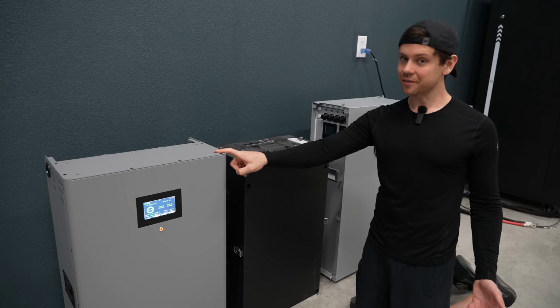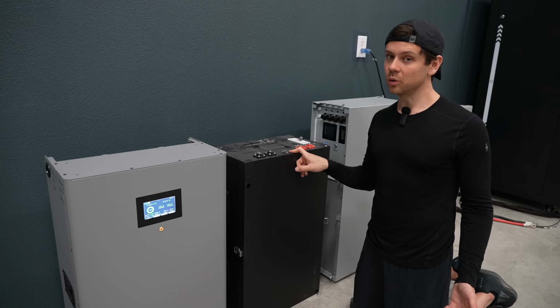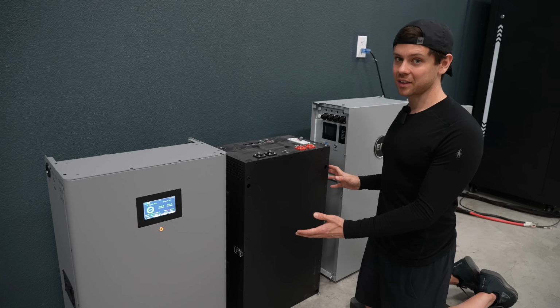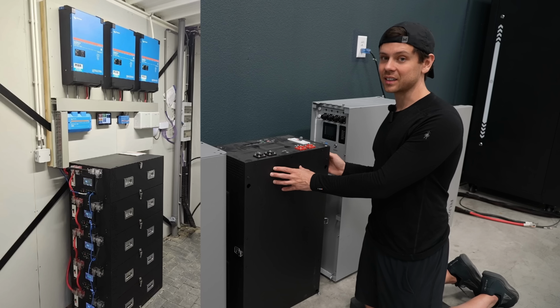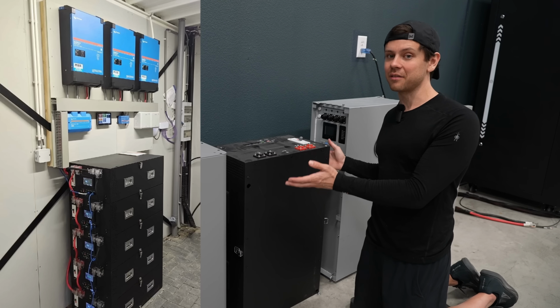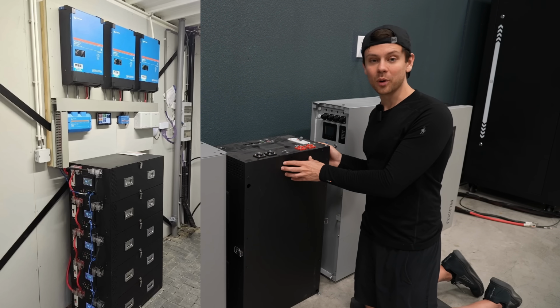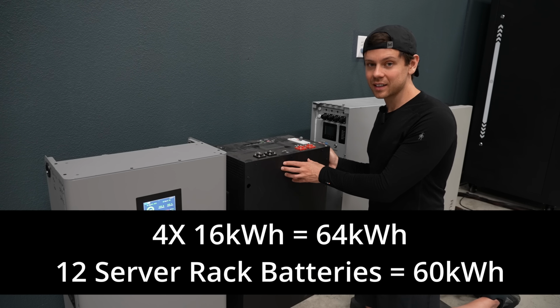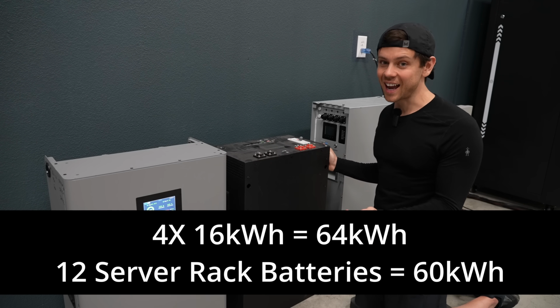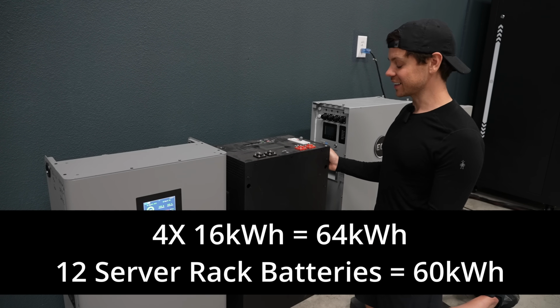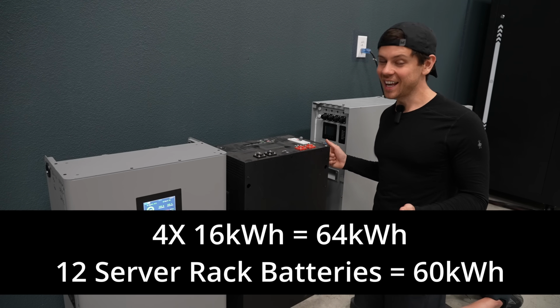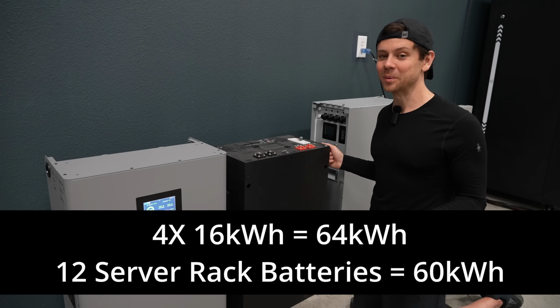Besides the fuse, I still like the horizontal one better because you can stack them. This has the best volumetric density out of, I think, any battery I've ever tested. If you stack 4 of these, you'll get the same capacity as 2 server rack stacks, which is crazy. But is it code compliant? If it's not UL listed, it probably isn't.